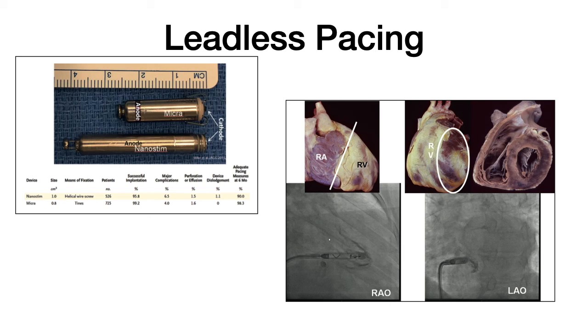The leadless systems have been developed using two distinct strategies, single-component and multi-component systems. With a single component, the entire pacemaker, the battery, electronics, stimulating electrodes, and sensors are compressed into a small capsule that is delivered into the heart using a deflectable sheath. The advantages of this strategy include greater energy efficiency, system simplicity, and ease of implantation. However, it has certain limitations that include the retrieval of the intracardiac system after battery depletion and uncertain thrombus and infection risk. With a multi-component system, a small seed is placed within the cardiac chamber to act as an energy transducer, and a second extrathoracic component beams the energy, usually either ultrasound or radio waves, to the seed, and this seed then converts this energy to a pacing pulse.